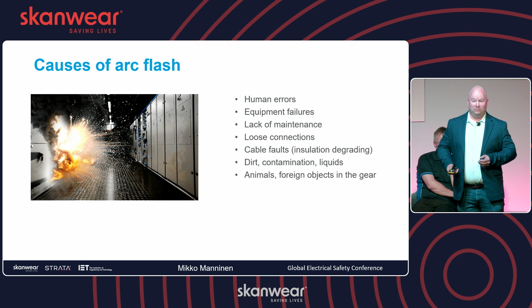Is maintenance a cost? For someone it can be a cost, but that cost will be much, much more expensive if it's lacking. Loose connections, animals like rats, for example. If you have a power plant, you have cooling water. If you have cooling water, you may have rats. And that happens. So here, before and after — this is quite self-explanatory. You cannot use the switchgear on the right-hand side anymore.